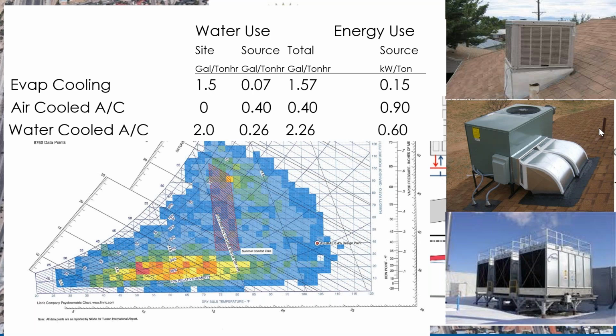This depends on how much demand is on the line - it's current loss. On a really hot day, when everybody's running their rooftop air conditioner and we have the highest loads, the wires become relatively undersized and there's more and more loss. It's real dependent on how much juice is flowing through them. Here in Arizona, our utility has kind of oversized our lines, so you don't hear a lot about high line losses in our grid. I'm guessing we're on the order of, on a hot day, 3-5% of energy is lost from the point it was generated at the power plant to the point at which you use it.